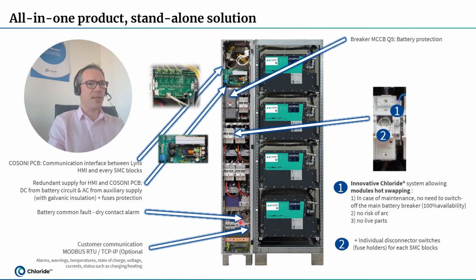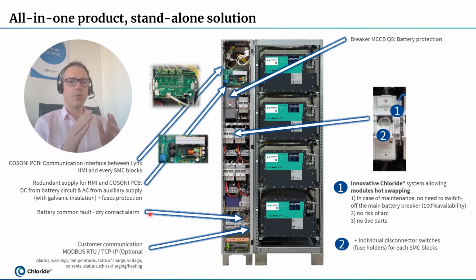Right there, we have integrated a battery common fault. It's a dry contact alarm, a volt-free contact, to connect your PLCs or SCADA system directly to this cabinet. We can integrate in options the customer communication Modbus RTU or TCP over IP, and through this Modbus communication, you can read with any PLC the alarms, the warnings, temperature, state of charge, voltage, current, and status, such as charging, heating, when the battery is warming and so on.